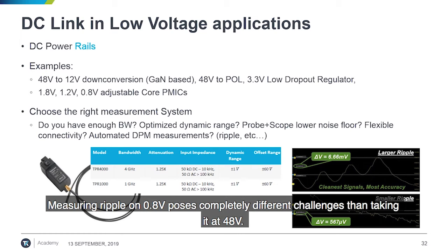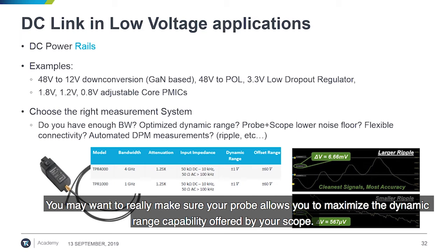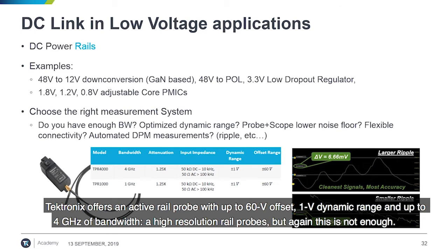Measuring ripple on 0.8 volts poses completely different challenges than at 48 volts. So you want to make sure your probe maximizes the dynamic range capability offered by your scope. Tektronix offers an active rail probe with up to 60 volt offset, 1 volt dynamic range, and up to 4 gigahertz of bandwidth - a high resolution rail probe, but again, this is not enough.